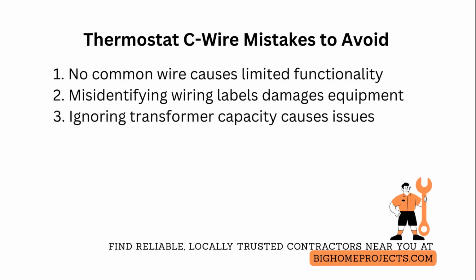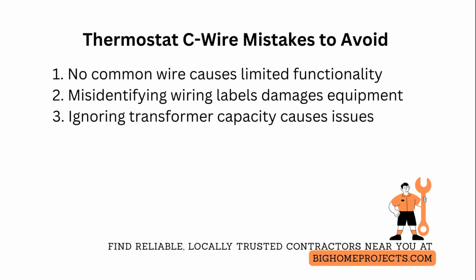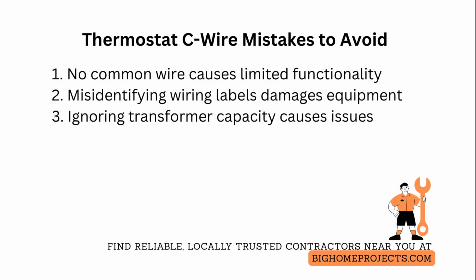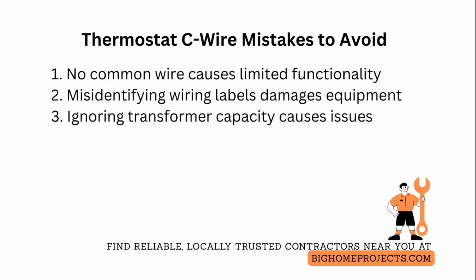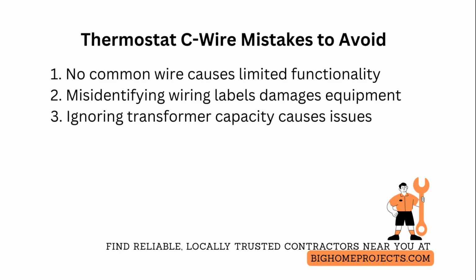The third common problem is ignoring transformer capacity and converter compatibility, which leads to tripped circuits or intermittent behavior. Fix this by measuring the transformer output under load, comparing it to the thermostat current draw, and installing a higher capacity transformer or a dedicated power supply if needed.